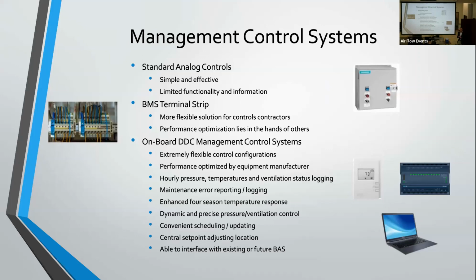You also have tons of information readily available at your fingertips with these systems. So you're constantly logging things like building pressures, building temperatures, outside air, return air damper positions, VFD speeds. All of that information is readily available. So when your facility manager goes and looks at what's actually happening in the space, you can say, okay, this is a big problem. We have to fix this certain thing, and it might be a controls change, or it might be something more serious like a design change. But at least they have that information available to make those educated guesses.